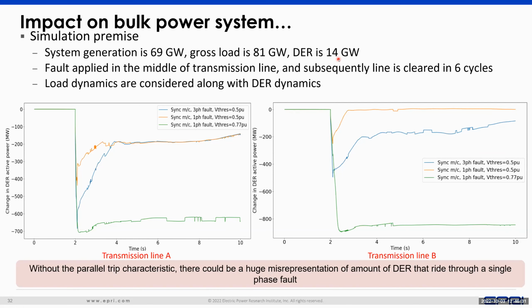So you have an entire large network of this. Now, if you consider two scenarios, wherein for transmission line A we apply a single line to ground fault, in the scenario where everything is represented with the same fault, if it is a three-phase fault instead, you would see the blue curve, showing an approximate 200 megawatts of DER tripping.